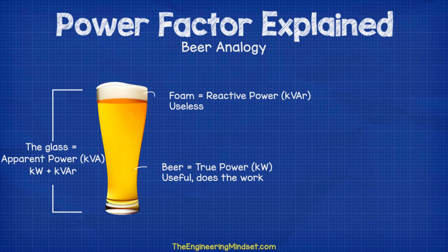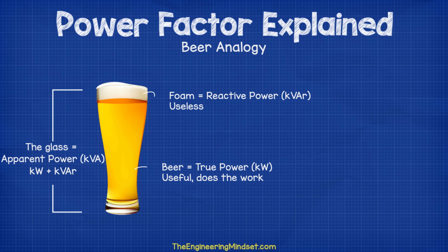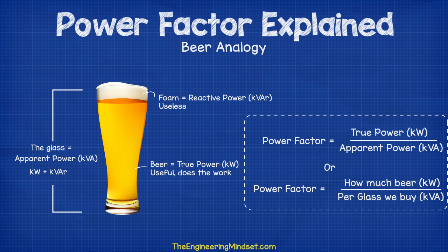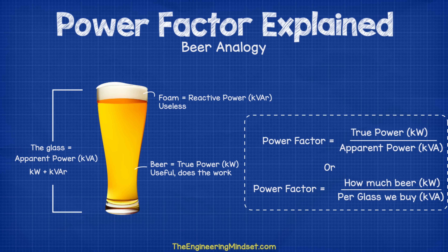The combination of our KW, our kilowatts, and our KVAR, the kilovolt amps reactive, is our apparent power, or our KVA, meaning the kilovolt amps. Power factor is therefore the ratio of useful power, or true power, in kilowatts divided by what we're charged for in KVA, the kilovolt amps. So it's telling us how much value for money we're getting for the power we consume.